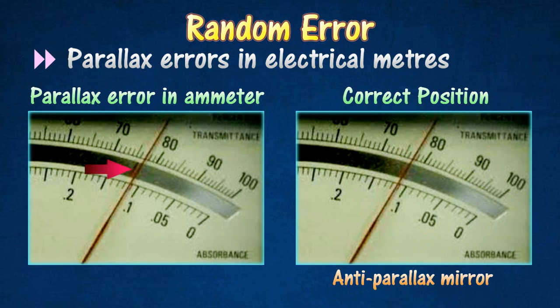Electrical meters normally come with an anti-parallax mirror. To avoid parallax error, the position of the eye should be adjusted so that the image of the pointer in the mirror is directly under the pointer. In the correct position, the image of the pointer cannot be seen.